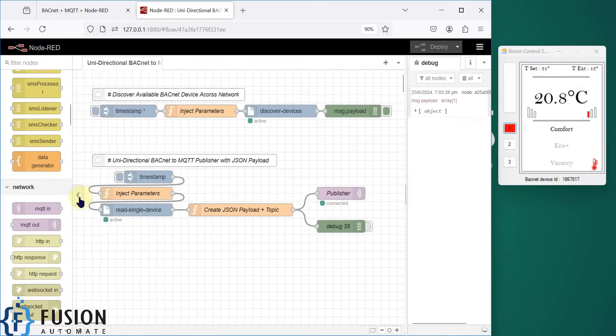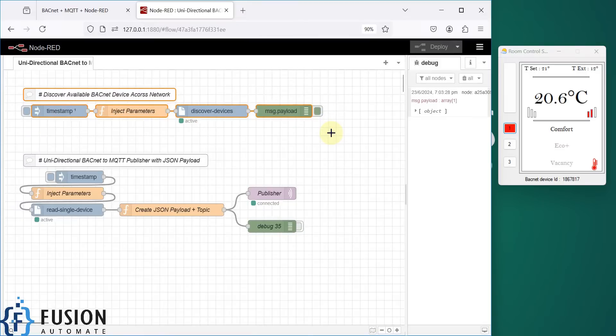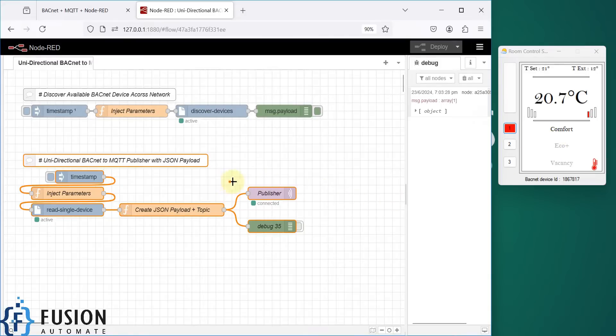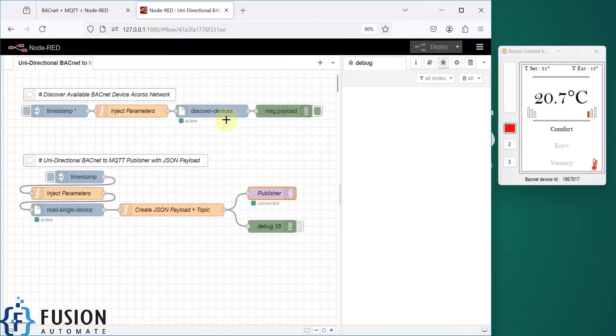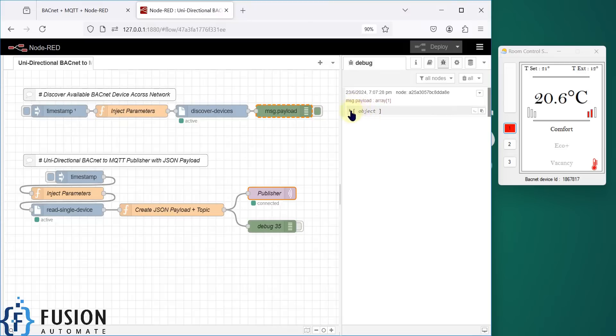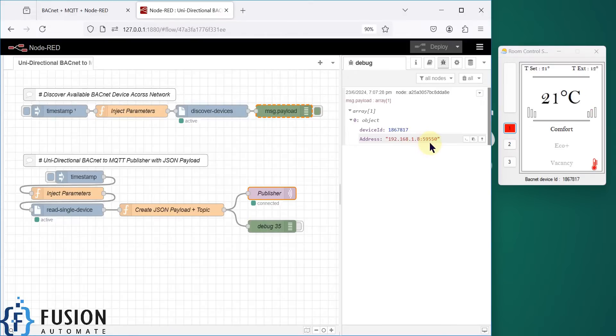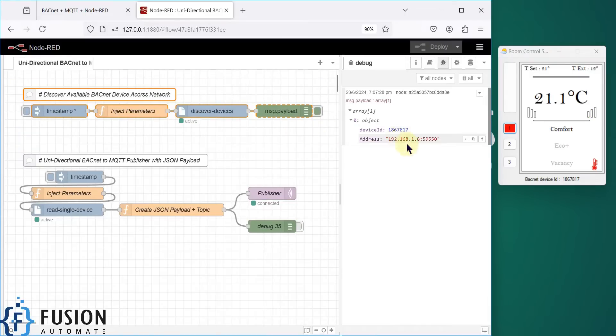In this flow there are two sections. The first section discovers available BACnet devices across the network. The second section reads data from a specific device and publishes all the data to the MQTT broker using the publisher node. Let me clear all messages from the debug window and inject the timestamp. Once the timestamp is injected, it will find the available BACnet devices in the network. You can see a result — IP address 192.168.1.8, port number 59550, and device ID 1867817, which matches the simulator.